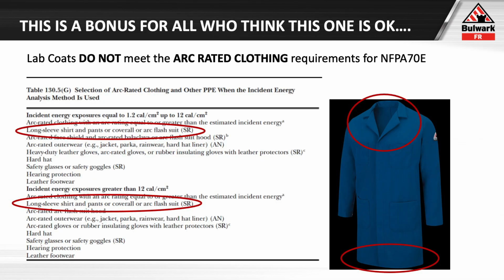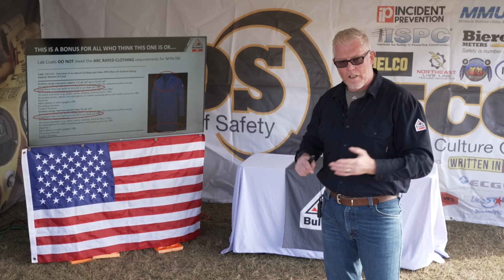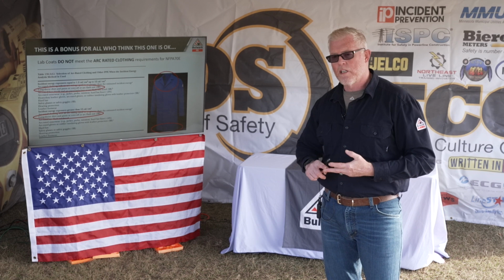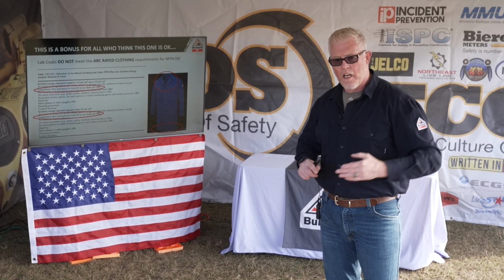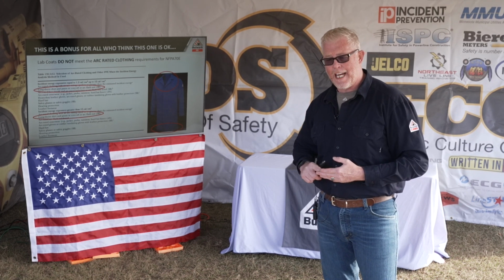The other thing we've seen, especially in general industry and in some substations, is flame-resistant arc-rated lab coats used as PPE for our hazards, but they're not. If you read the definition of the garment, it says lab coats — that's the only place these garments should be utilized. 70E, for example, spells out long sleeve shirt, pants, and/or coveralls, regardless of the incident energy you're looking at.